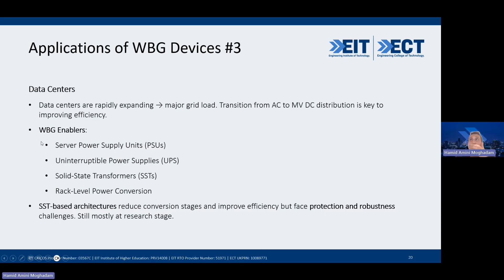So what happens is wide bandgap devices enable direct high voltage AC to DC conversion, right? And that can happen at the rack level, directly behind the server. And this minimizes the distribution losses because that happens right at the rack, not somewhere else, and then bring it there. And that allows for more efficient power delivery to the server. Generally speaking, system level, if you have wide bandgap switches, you are reducing your cooling requirements, you have a smaller footprint, and you have better reliability when it comes to data centers. So these are the benefits of wide bandgap.